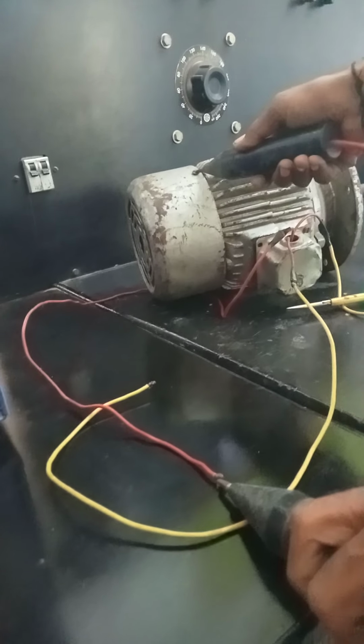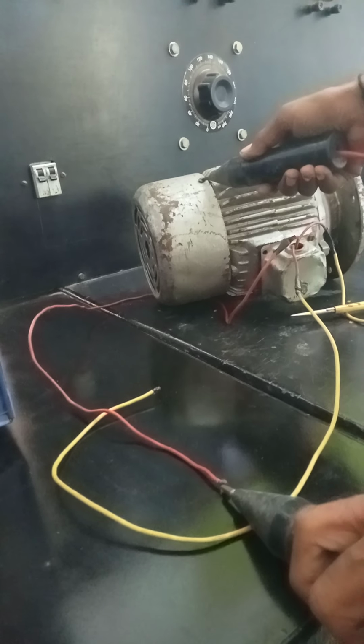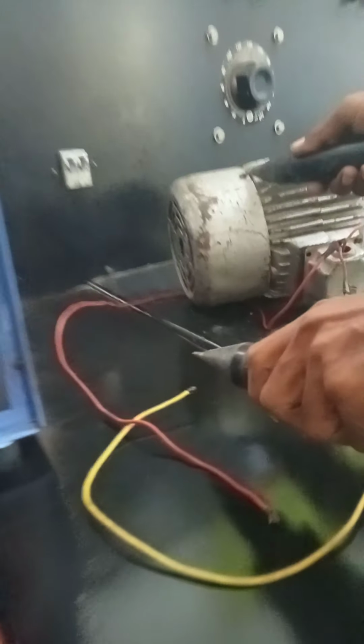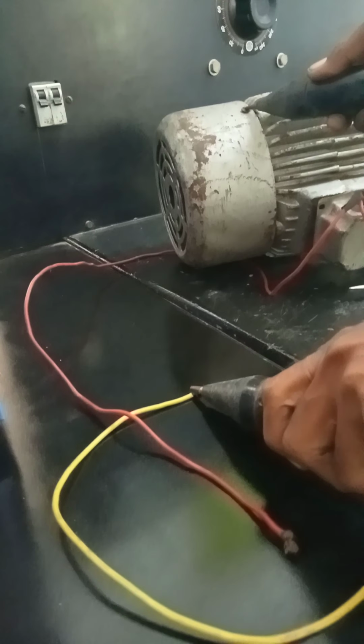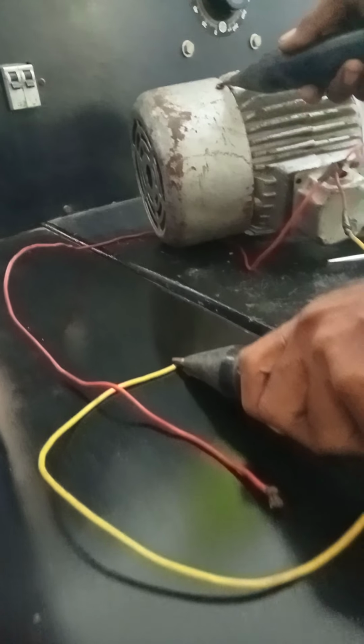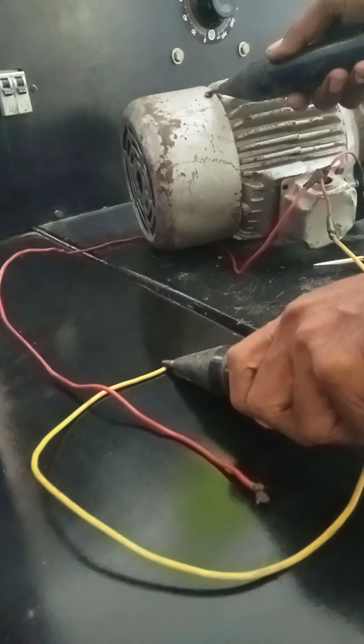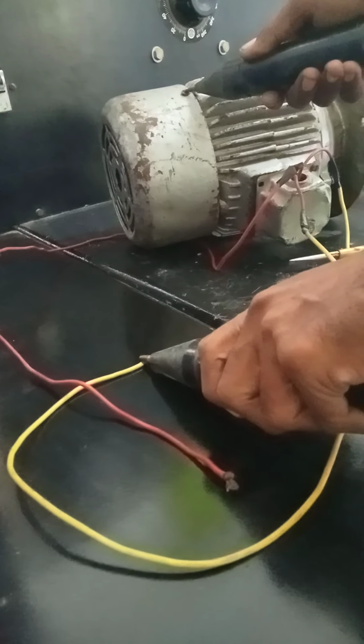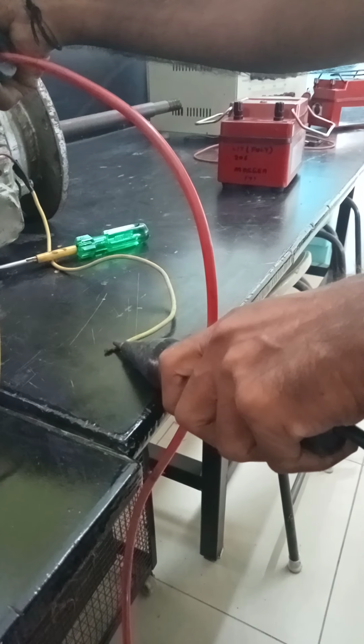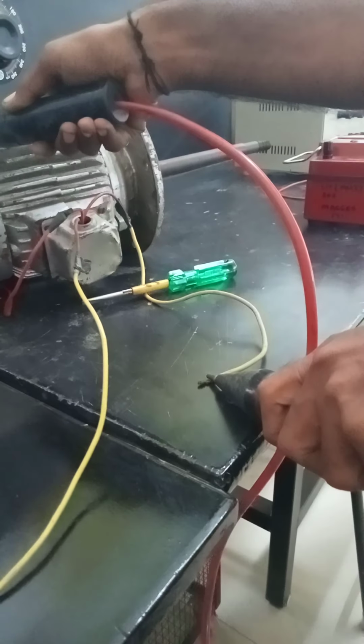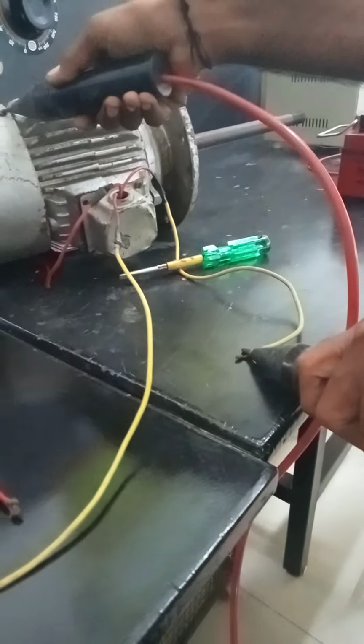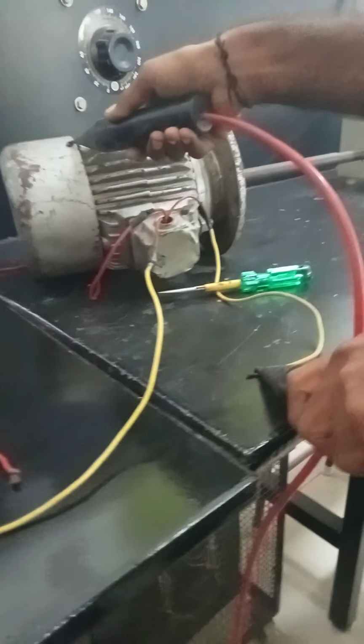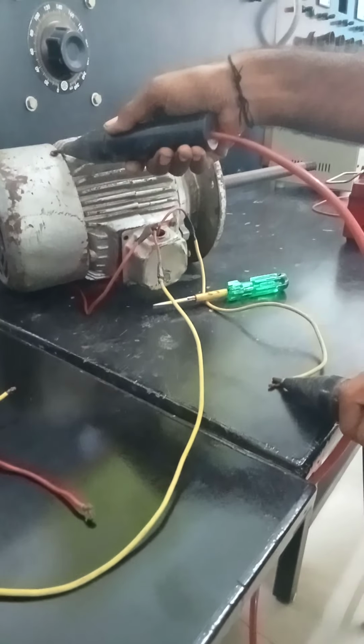That means the insulation across this phase is good. Now I will connect it with another phase. See, again no buzzer sound is coming. This indicates that the insulation resistance is high across the phase winding. Now we will connect it with the third phase. Again no sound is coming. That means the insulation resistance of this phase is also high.